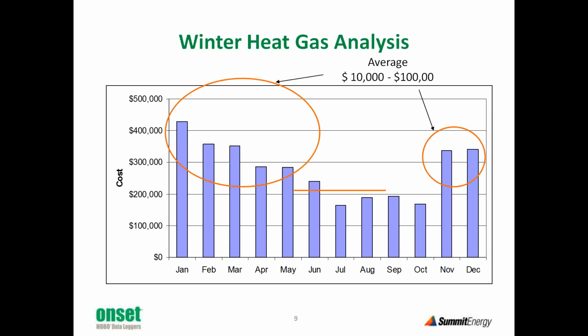Another interesting analysis that I recommend is quite simple. Take your gas bills each month and line them up for a year. If this were a factory, I would make the assumption that the gas usage through the June, July, August time frame, in the northern hemisphere that would be the summer, is the gas usage associated with the production facility. Then we're interested in looking at the winter gas, the extra gas that is used in the wintertime for heating. This would give us an idea of the potential value of the heat recovery.